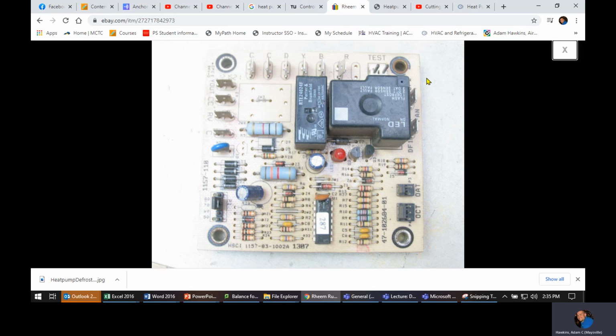So if that board can take that out, the board could have it out. The way you would check that is you would just check across your switches, and if you're not reading 0 volts across that, then that's probably bad. And so you can actually jumper that temporarily if it's in cooling and get you through until you can get another board. There's other ways to jumper a board, and I'll show you that in a future post. But you also got test terminals on here. This one doesn't give you directions on how to test it, but I'm assuming most of them you short these test terminals, and then that's going to allow you to force it into defrost.